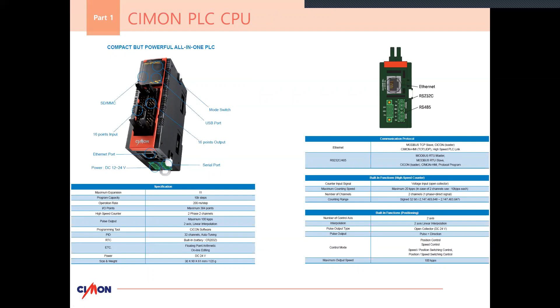A little something that's notable about the PLCS is that when it comes to the Ethernet port, it can accept Modbus TCP slave, but it cannot do Modbus TCP master. You would need an Ethernet card that's dedicated to that. On top of that, it provides serial Modbus master and slave. So if we look right here, it can do Modbus master and slave through serial, but just slave through Ethernet. You would need the dedicated Ethernet module, just to reiterate that point, if you want to do Modbus master with the PLCS.